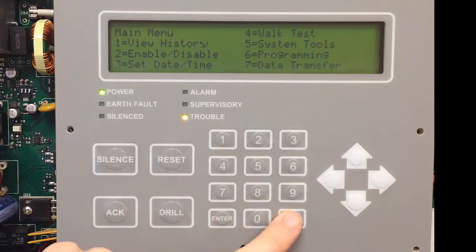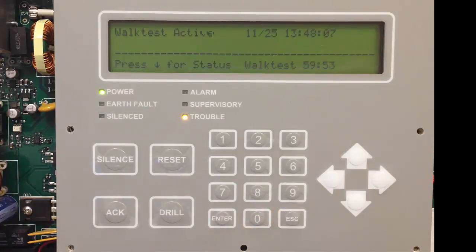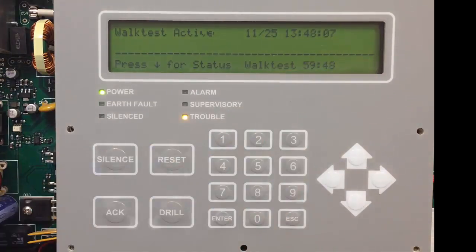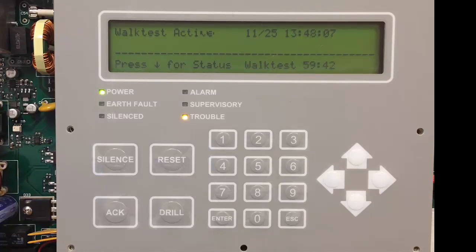At this point we're in walk test. If you escape out to the main menu, you'll see your walk test is active. There's a 60-minute countdown — as soon as the first device is tested, that will restart to 60 minutes. That is an inactivity timer. If nothing is tested within 60 minutes, the system will reset and it will go out of walk test.